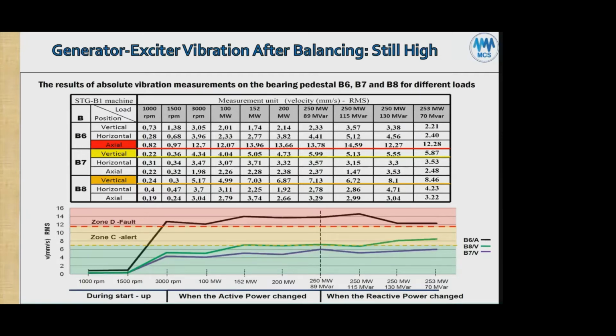Okay. So we also have high vibration, as we said, on the B6, B7 and B8 bearings. The highest we can see here is on the axial, 13 millimeters per second. We have on the radial B7 vertical, 6 millimeters per second. This is not disastrous. Then we have.